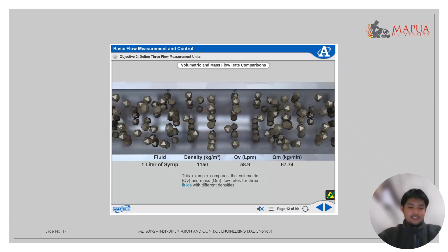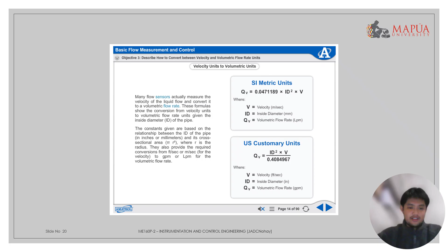Velocity units to volumetric units. Many flow sensors actually measure the velocity of the liquid flow and convert it to a volumetric flow rate. These formulas show the conversion from velocity units to volumetric flow rate units. Given the inside diameter ID of the pipe, the constants given are based on the relationship between the ID of the pipe in inches or millimeters and its cross-sectional area, πr squared, where r is the radius. They also provide the required conversions from feet per second or meters per second for the velocity to GPM or LPM for the volumetric flow rate.